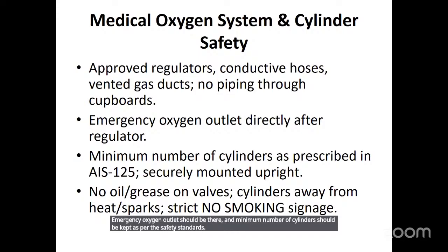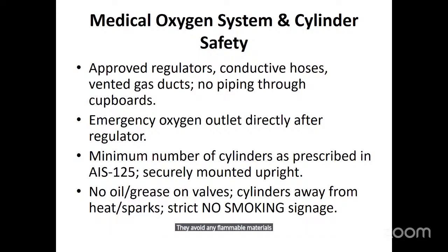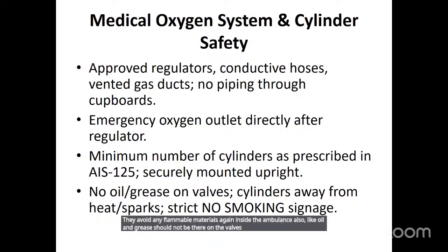They avoid any flammable materials inside the ambulance also, like oil and grease should not be there on the valves. They should be clean, and the cylinders should be kept separate for the purpose of transportation. The hospital cylinders usually have dirt, oil, grease on them, which can actually trigger sparks.